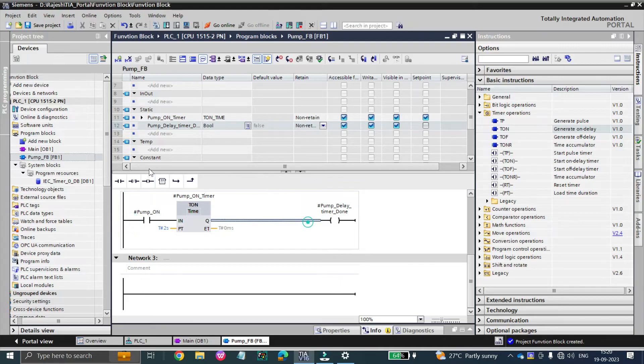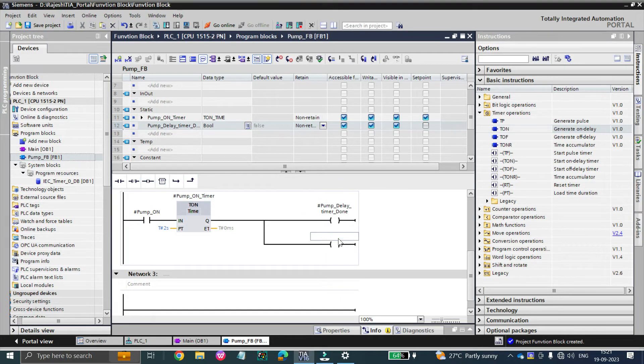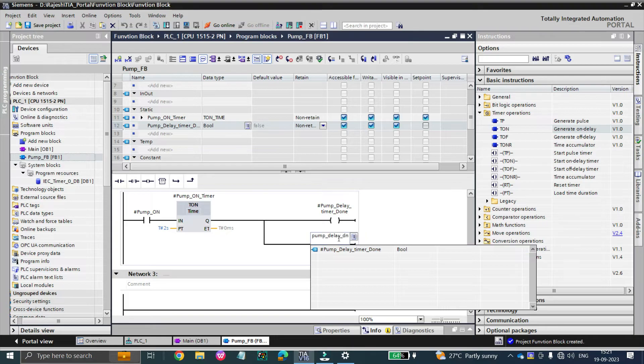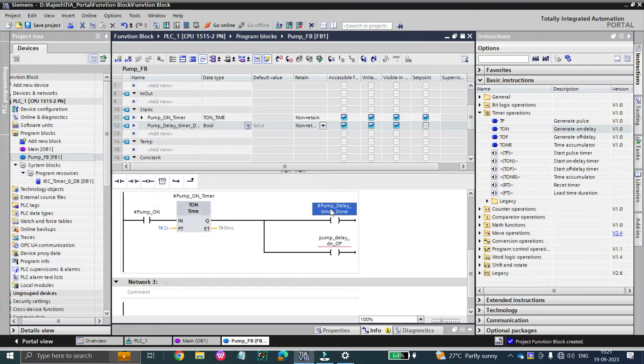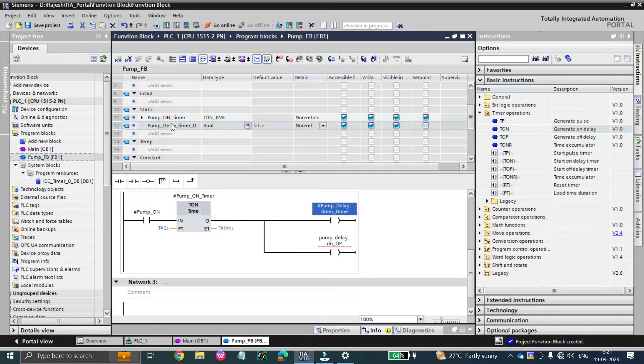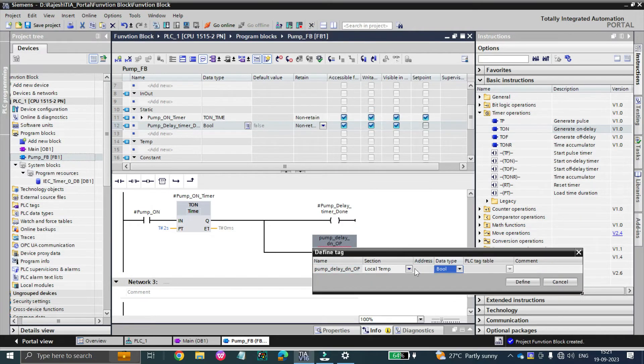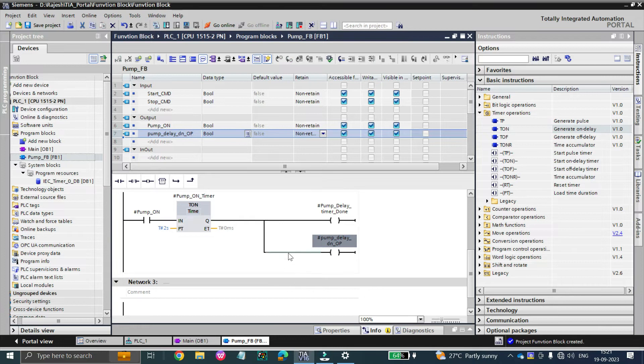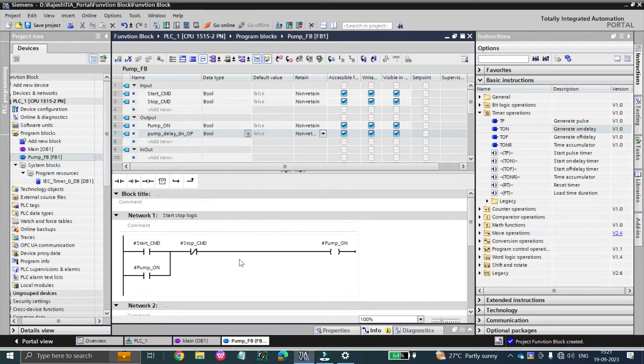We can also turn on another output called pump delay done op. The difference between pump delay timer done and pump delay done op is this: if you want a memory bit stored in static only, you keep it in static. But if you want to access the timer output outside of the function block, you have to store it in the output local tag instead of the local temp tag. You can see the pump delay output is now being created in the output section. So our simple function block logic for the pump is now created.